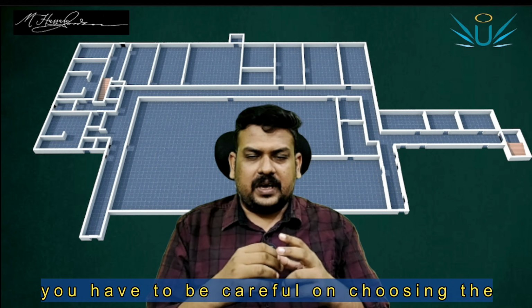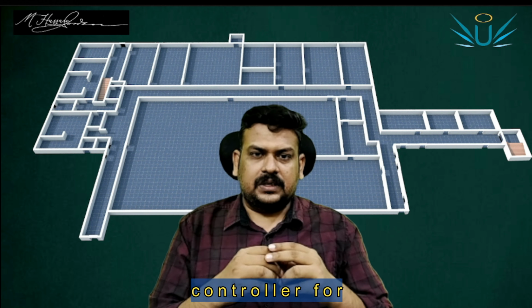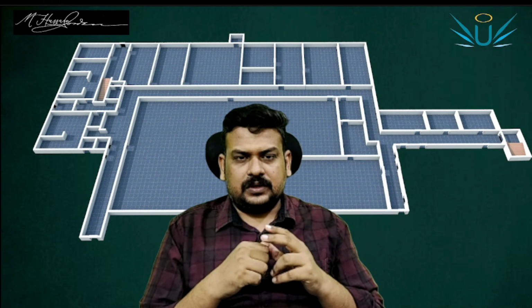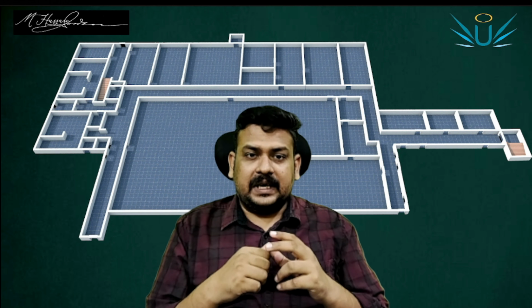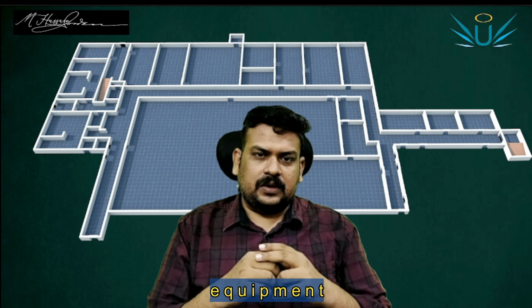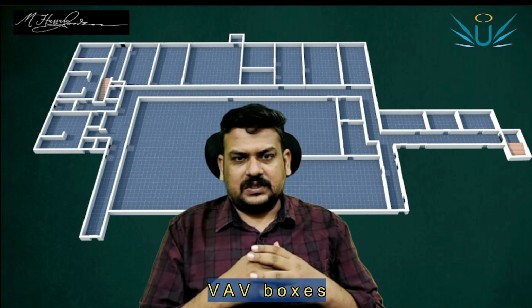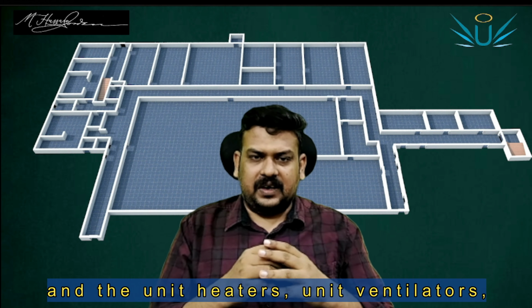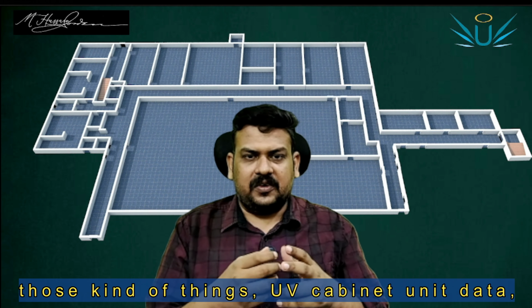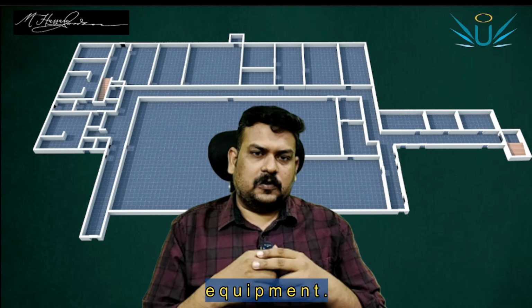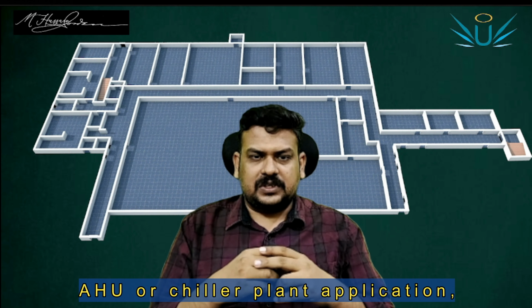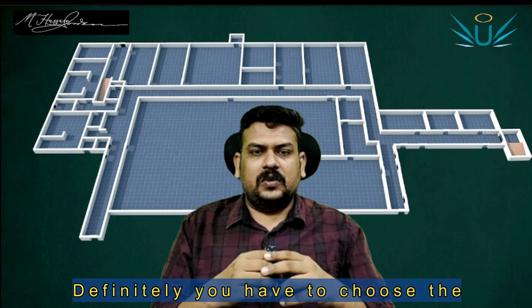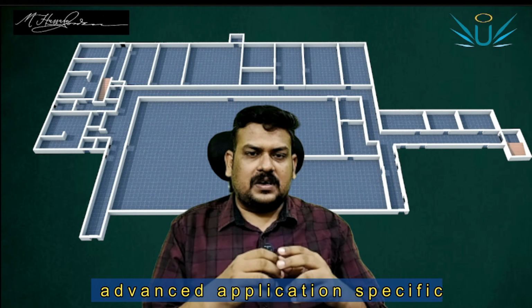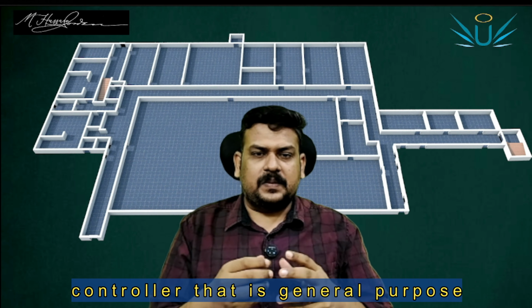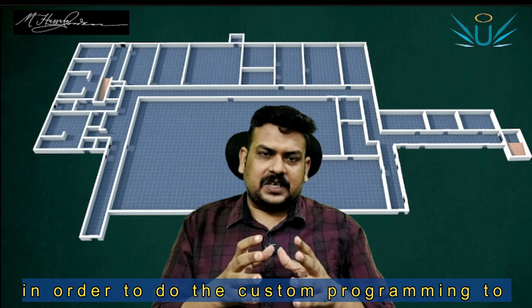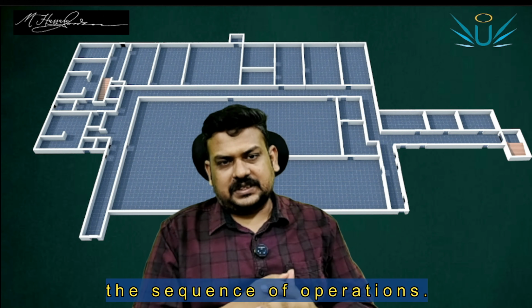So if you look at the specification, and if you are an estimator or a designer, you have to be careful in choosing the controller for the HVAC equipment. If you are going to choose the ASC, that equipment will definitely be VAV boxes, unit heaters, unit ventilators, cabinet unit heaters, that kind of small equipment. And if you are going for an AHU or chiller plant application, definitely you have to choose the advanced application specific controller, that is the general purpose application controller, in order to do the custom programming to meet the sequence of operations.